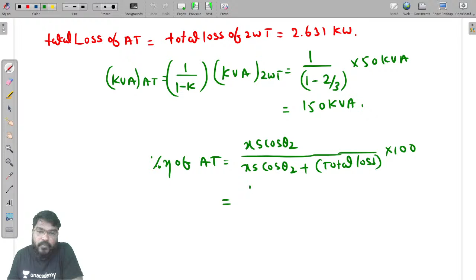Okay, what's the answer? After getting the kVA, now find out the percentage efficiency of the auto transformer, which is equal to X·S·cos θ2 divided by X·S·cos θ2 plus the total loss of the auto transformer, multiplied by 100. X value: given that efficiency is at new rated load at unity power factor. So now 1 into 150 into 1 divided by 150 plus 2.631 kilowatts, multiplied by 100. Now calculate.